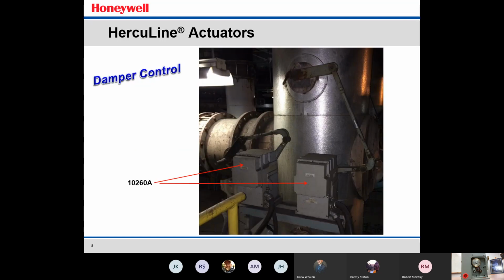Here's another application. This is a Herculine 10260. This is the A model. Again, connected up to some very large dampers. There's a damper on the top and then also a damper off the side. These are applications that require a little bit higher torque usually. You'll typically see these in large plants, glass manufacturing, steel manufacturing. Those are pretty typical. Also, Leeds and Northrup back in the day was really big in the power utility, and you'll actually see a lot of 10260 actuators throughout the power industry as well.